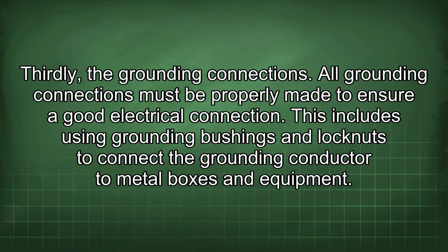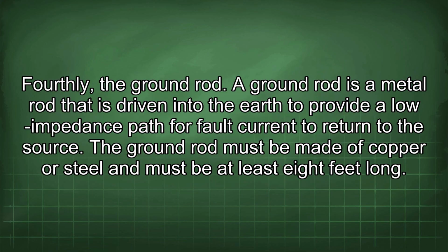Thirdly, the grounding connections. All grounding connections must be properly made to ensure a good electrical connection. This includes using grounding bushings and lock nuts to connect the grounding conductor to metal boxes and equipment. Fourthly, the ground rod. A ground rod is a metal rod that is driven into the earth to provide a low impedance path for fault current to return to the source.